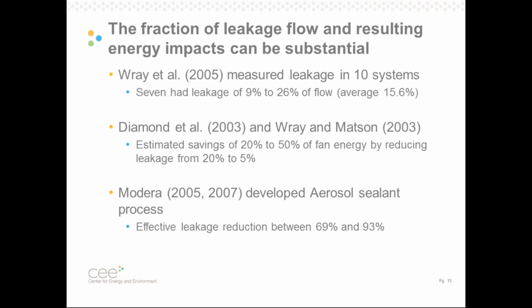Most of this work came out of California over the last 10 or 20 years. Researchers there initially started measuring duct leakage in relatively low pressure systems. For example, Wray in 2005 showed that measured leakage in 10 systems averaged about 15%. 70% of the systems had leakage of 9% or greater, and they only found 3 systems that they called tight. The same group also did some energy modeling and in some cases measurements to show that if you do seal this leakage, you end up with significant fan energy savings on the order of 20 to 50%.